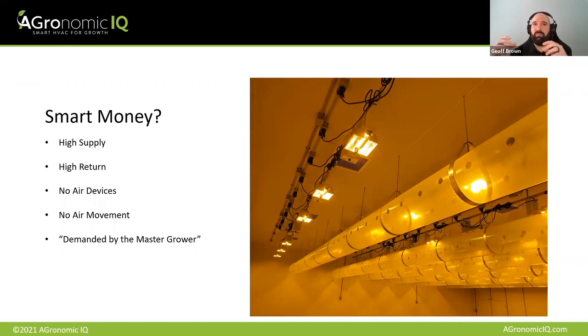Again, any plug load in that space, any energy you spend in that space, you also have to spend energy cooling. So if you have a horsepower of fan in your room, you've now got an extra, call it 3,000 BTUs that you have to cool every hour. So there's an energy cost to running the fans, and then there's a second energy cost in cooling the fan energy. But in this case, there are no air rotation fans. There's nothing getting the air to a good part of the room.